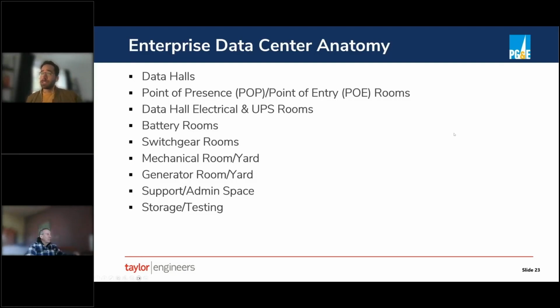Switchgear rooms, the distinction here between those and what I have above as an electrical room is essentially we're talking about medium voltage switchgear. You often see these in a separate room from the, say, 480 volt stuff that's going directly into the white space to serve the servers. There's almost always some sort of large mechanical room and often a mechanical yard as well. Generator rooms are required for backup power. So it's more often than not a generator yard, if they're outdoor mounted. Sometimes those generators will be mounted indoor and have external radiators.